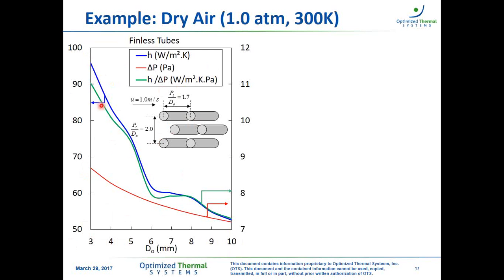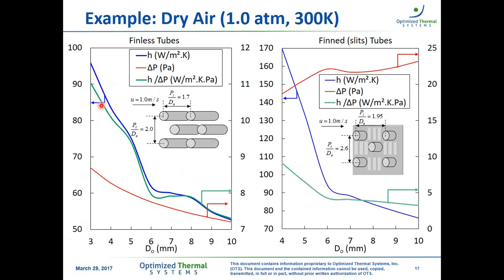Now, another example, an interesting example, because in this case we have a tube and fin, and the behavior is a bit different. So from a heat transfer coefficient perspective, it's behaving as we expect from what we discussed in the previous slides, though the pressure drop doesn't have the same kind of trend that we saw for the previous case. And what we're seeing here is actually a reduction in pressure drop, increase and reduction again. And there are reasons for that, and this is one of the things that we can leverage and play with when designing small tube fin heat exchangers.